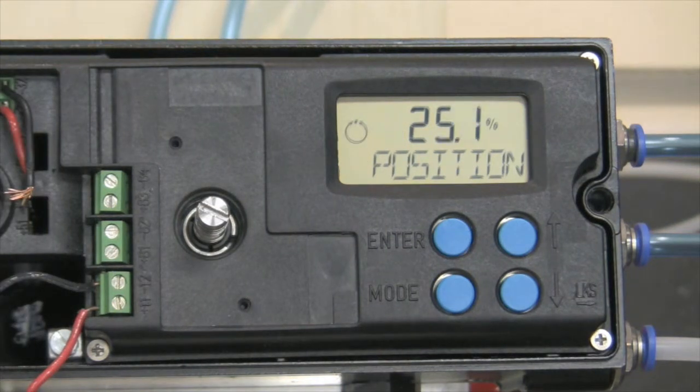Now that we've finished with calibration on our D400, the D400 puts it into control fixed. This is the calibration setting it learned here on the bench. But once we put this valve package into flow or into line, the dynamics on the valve and valve package will change. To optimize the performance of that valve package, we should put it into adaptive control.